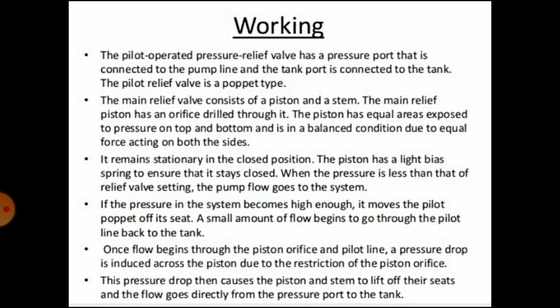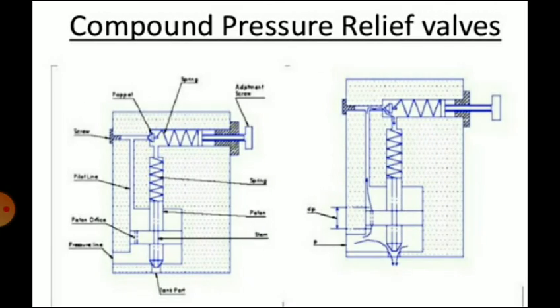The pressure applied at the end of the main stage is the same as the pressure applied to the cone of the small relief valve. Pressure difference occurs only when there is a flow through the orifice, and when there is no flow, pressure is equal on all parts it is connected to.